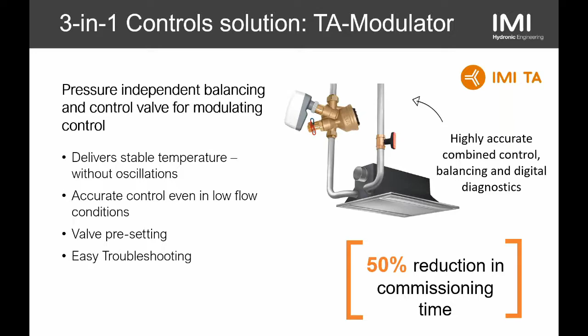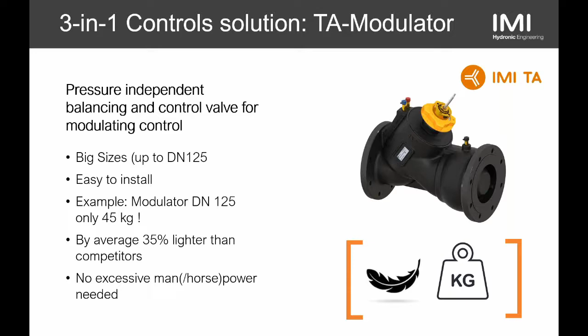A second important argument for our PIBCV valves is their weight. A heavy product creates a lot of installation worries. Here I have taken the DN125 as an example, and this PIBCV valve only weighs 45 kilograms. Our big size PIBCV valves are on average 35% lighter than competitor valves, so no excessive man or horsepower is needed.